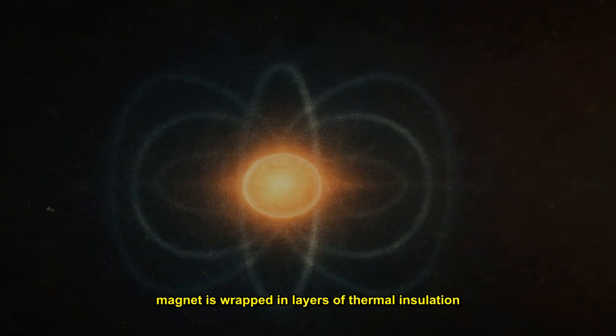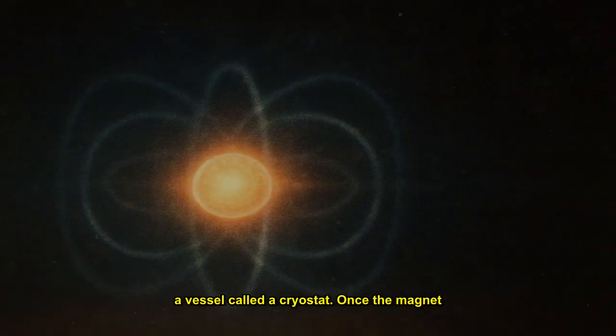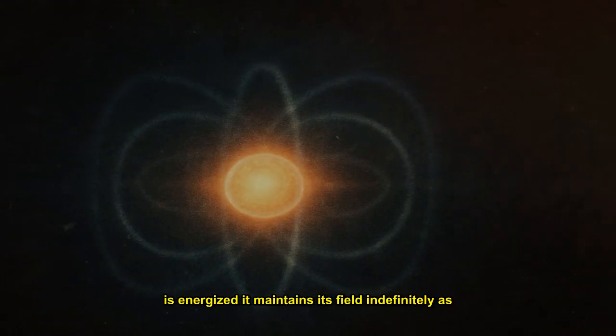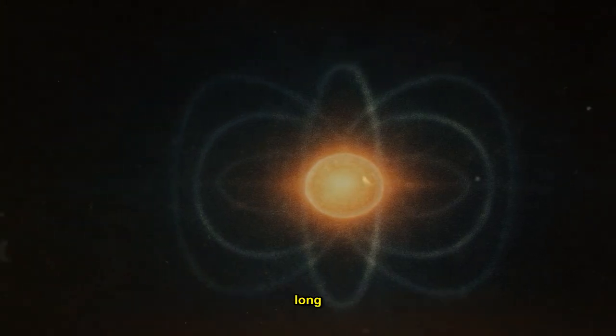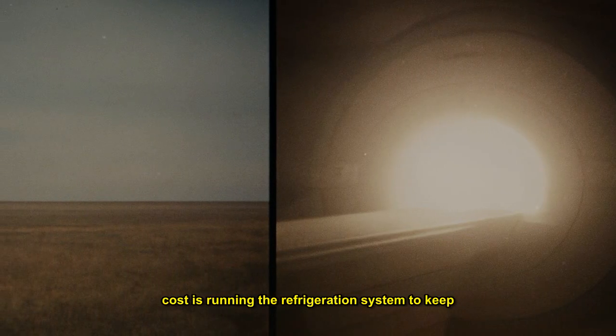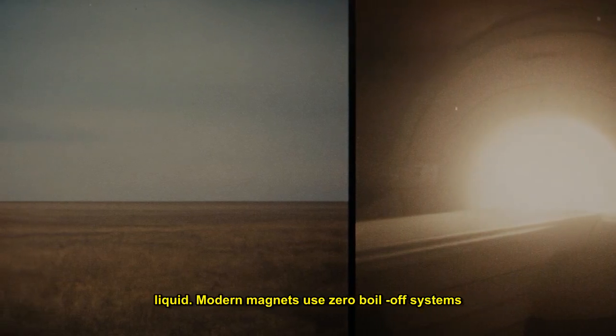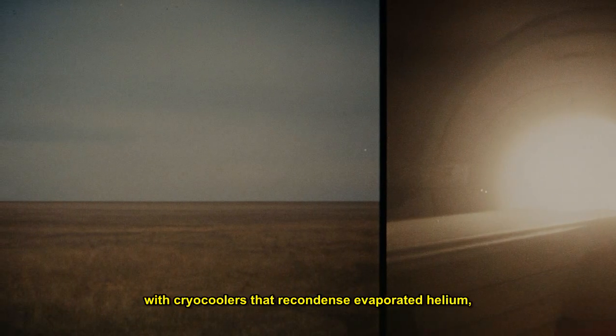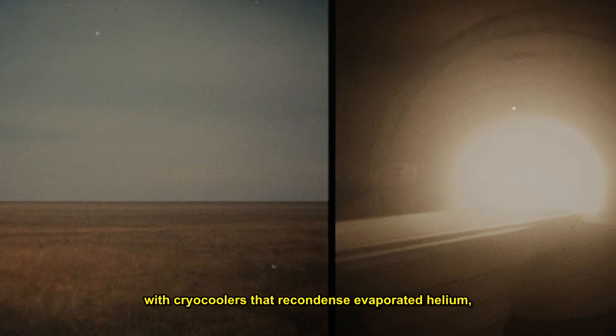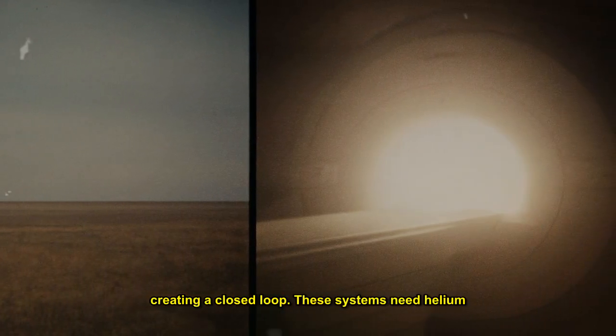The magnet is wrapped in layers of thermal insulation inside a vessel called a cryostat. Once the magnet is energized, it maintains its field indefinitely as long as it stays cold. The only ongoing energy cost is running the refrigeration system to keep the helium liquid. Modern magnets use zero boil-off systems with cryocoolers that recondense evaporated helium, creating a closed loop. These systems need helium refills only after a quench event.